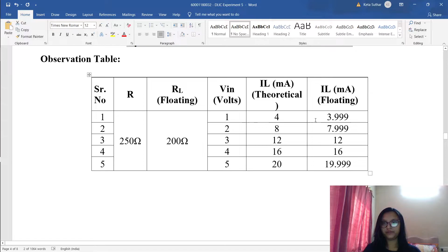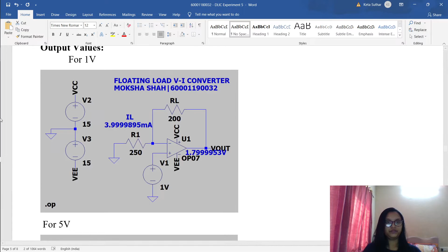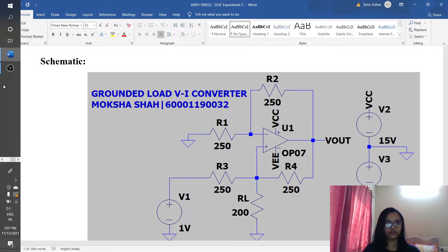For that, if I check, the IL value is nothing but 3.999, which is matching with my theoretical values. So RL is not affecting IL. If I check with 5 and run, the IL that I'm getting is 19.99 milliamps. The same thing I have written in my Word file. At 5 volts it's 19.99, and at 1 volt it is 3.99, that is approximately 4 milliamps. So this is for 1 volt and this is for 5 volts of the floating. Now I'll show you for the grounded.